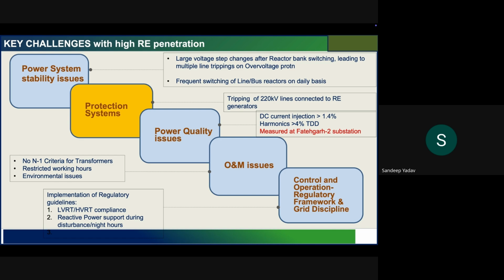However, depending upon what kind of control algorithm the OEM has used, the harmonics could be very different from one manufacturer to another, and that is why the grid code specifies what would be the DC current injection, what would be the individual and total harmonic distortion at the point of interconnection. Then there are operation related issues we'll talk about briefly in the upcoming slides. And later we need to put some systems into place as far as the grid discipline is concerned.